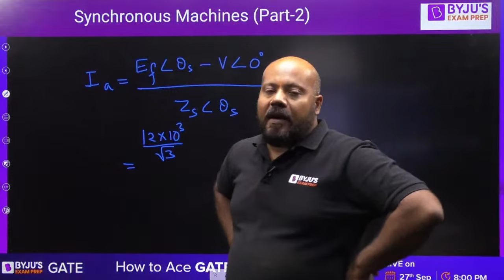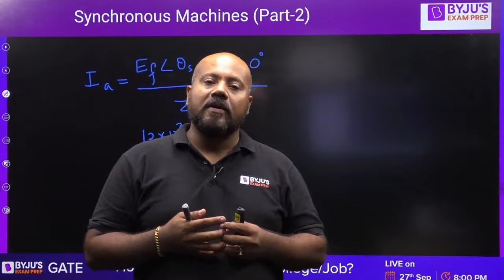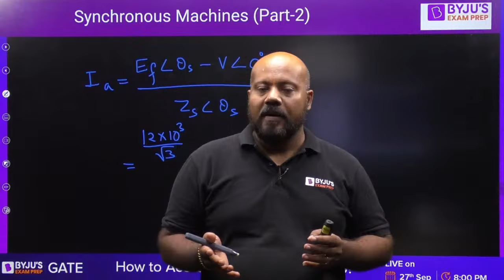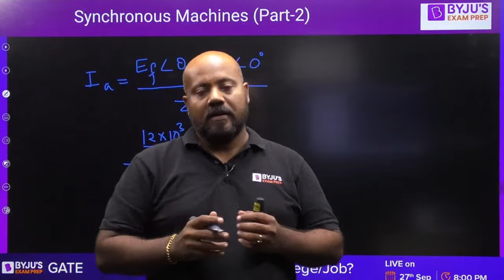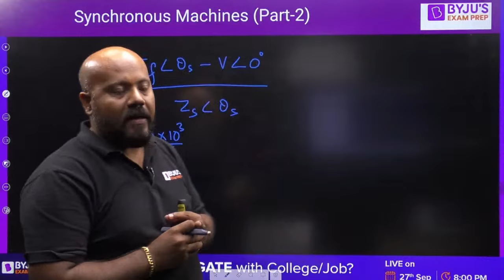Vishwanathan is asking, sir, current is... see, that MVA is given as the rating of the machine. Okay, that will give you the current only in case of full load conditions. Are you getting this or not? Yes or no? So depending upon the terminal voltage, you have to decide what is the current going through the generator to the bus bar. Directly you cannot write like that, otherwise it is going to be fundamentally wrong.